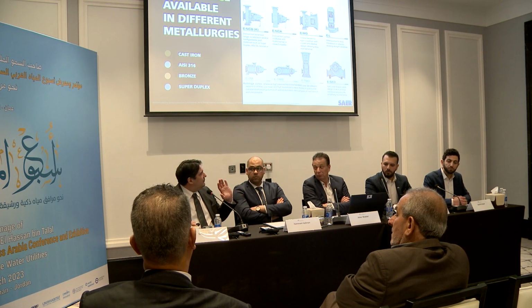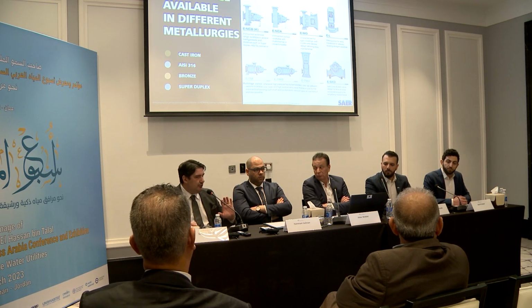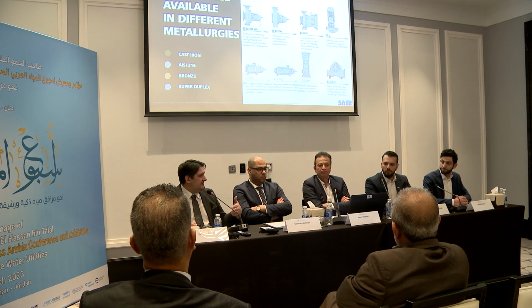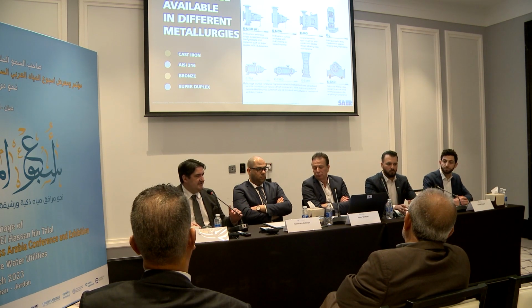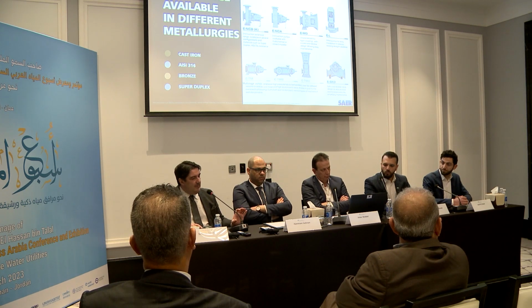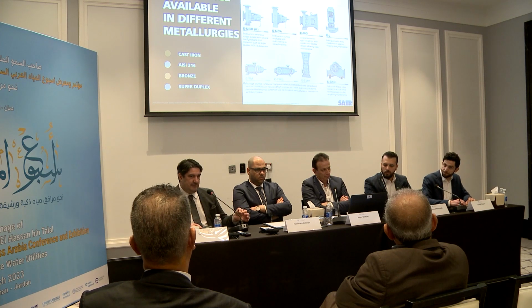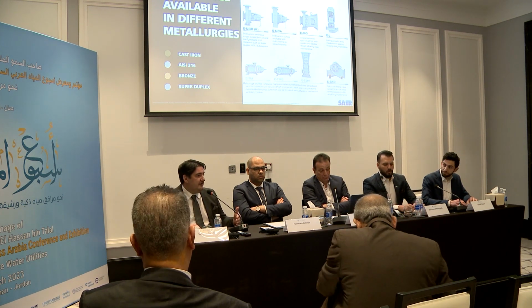I don't want to concentrate too much on the range of pumps, because it is just to show you that the type of pump must be chosen according to the existing system. So it is very important to design the system in order to save as much energy as possible. Consider that the average efficiency of a centrifugal pump, and my colleague Philo will talk about this, is around 75 to 85%, depending on the type of pump. A pump as turbine loses a little bit of efficiency compared to the same product used as a pump, around 5-6%. So it means that you can reuse 70-75% of the real power hidden in the water.